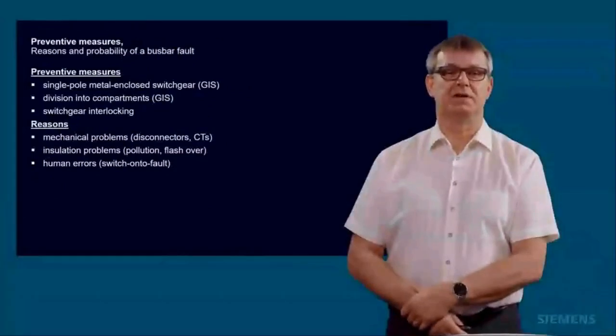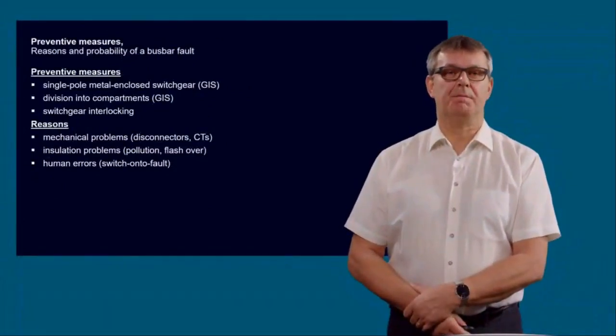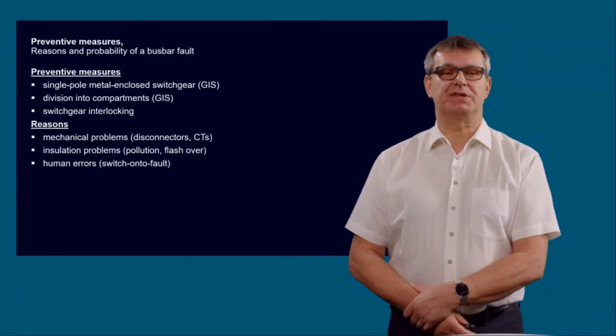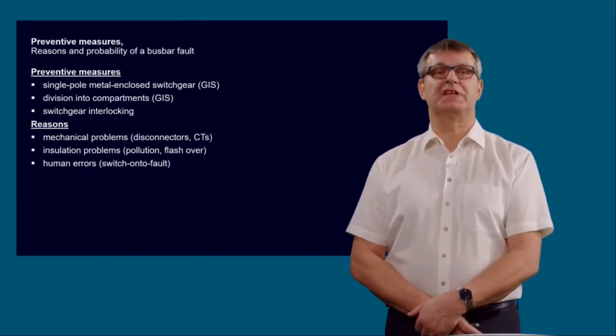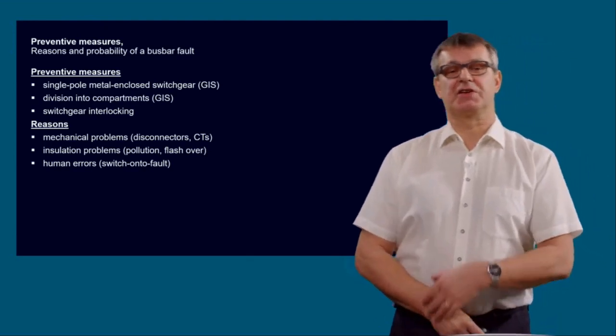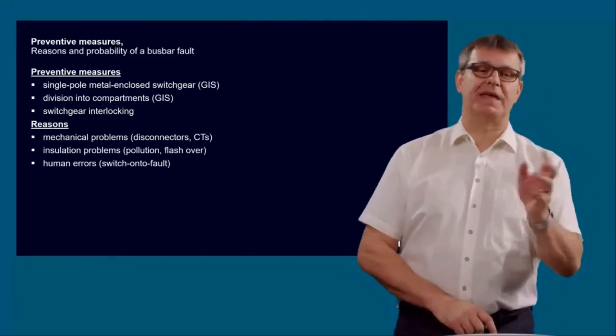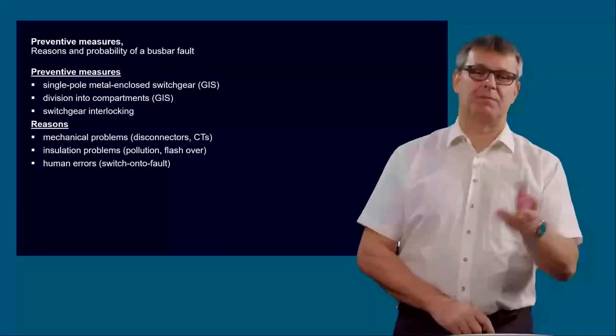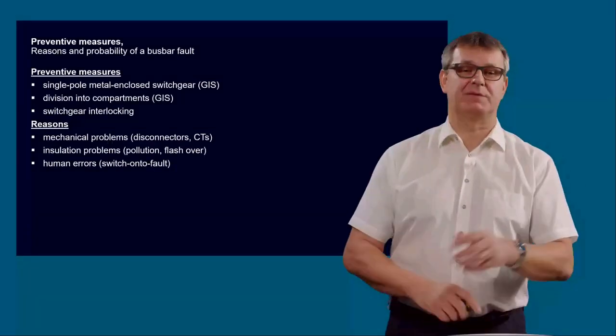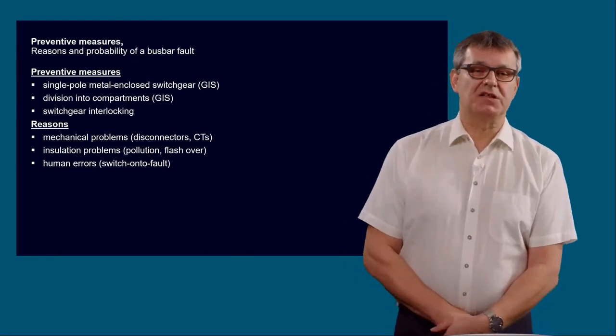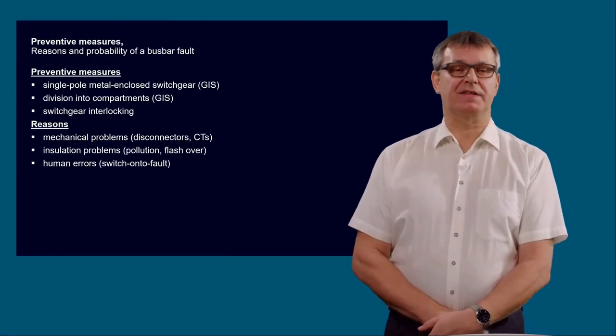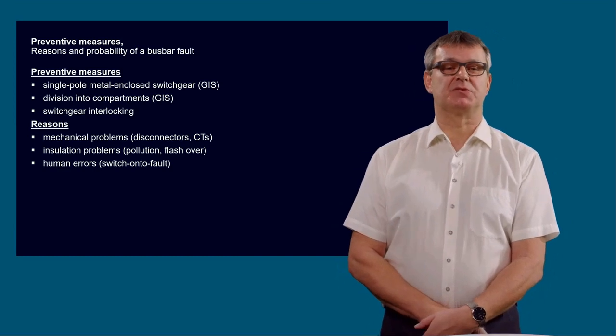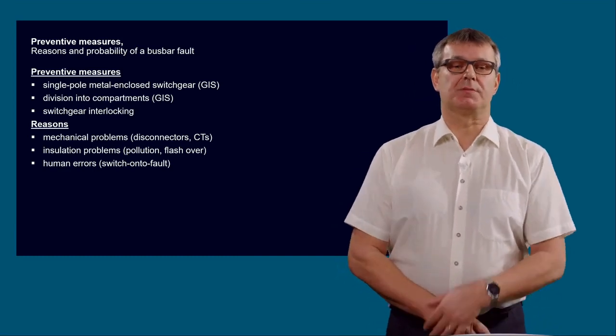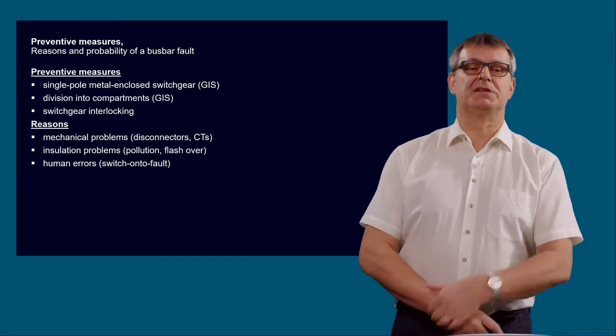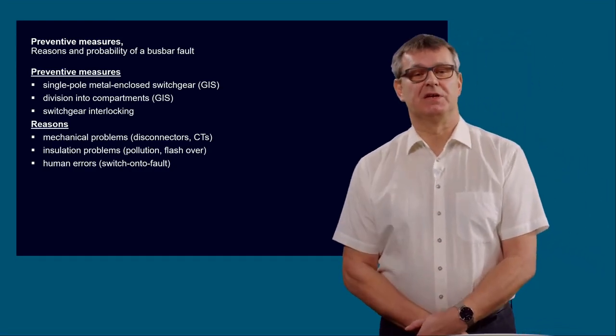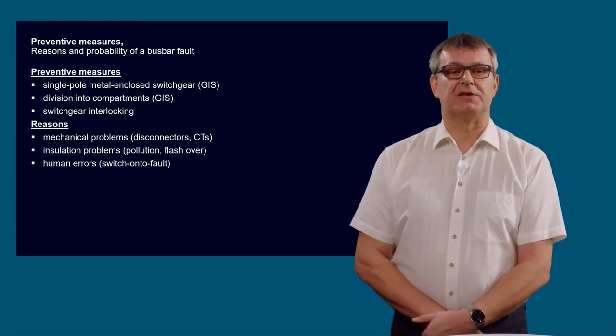What are the reasons? The reasons are mainly mechanical problems, especially problems during the running time of the disconnectors, sometimes mechanical problems of the CTs, but mainly of the disconnectors, and sometimes also mechanical problems of the circuit breaker. Not so much a problem in GIS stations, it's more a problem in air-insulated substations, is to have isolation problems, pollution flashovers. We have seen this in our short video at the beginning. This was most likely an isolation problem.